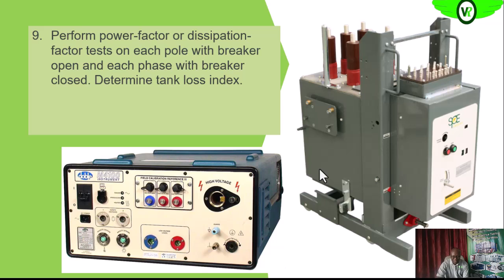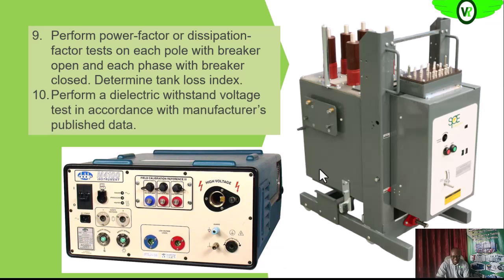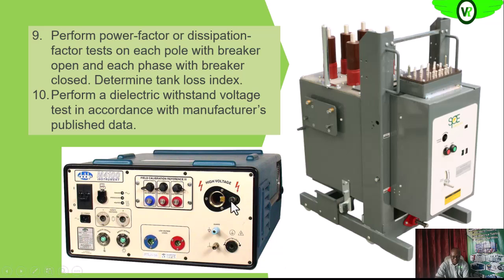We also perform power factor tests, which is also an insulation resistance test. Okay, so for the power factor test, if you are not too familiar with it, you can check the description below for a link to our training on the tan delta tests, or the power factor test and dissipation factor tests. Okay, then you will also perform the dielectric withstand voltage test. So we subject it to a very high voltage, more than what is normal, and then see if the insulation will be able to withstand that voltage. So all of them are basically to check the integrity of the insulation of the circuit breaker.